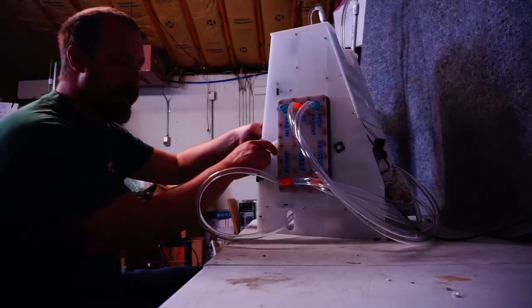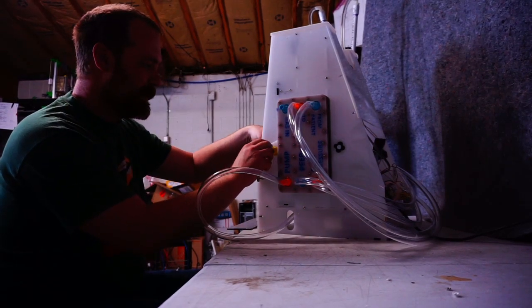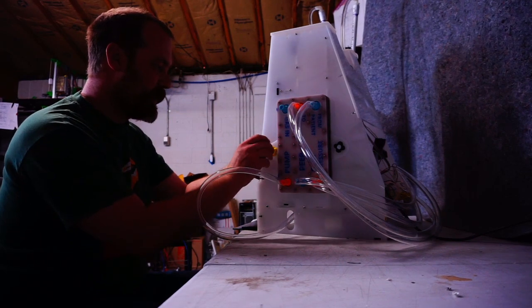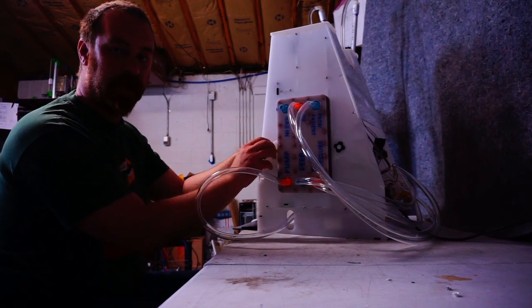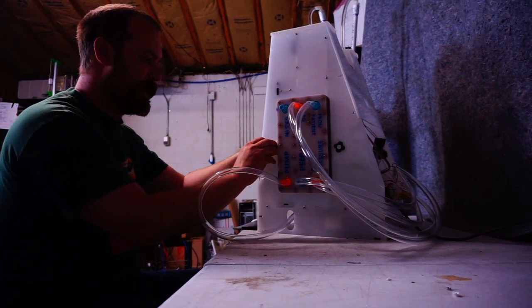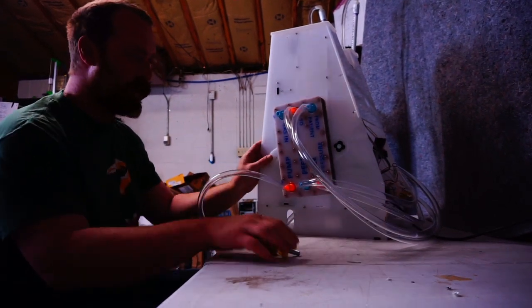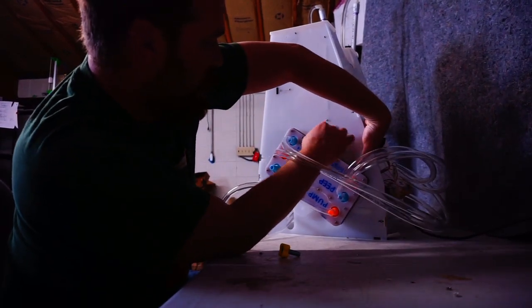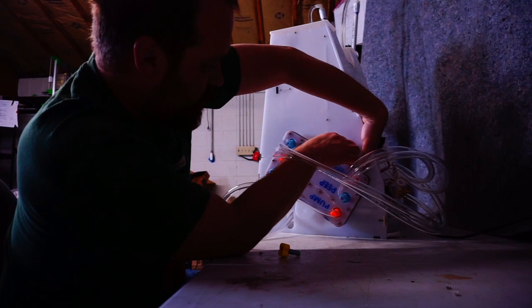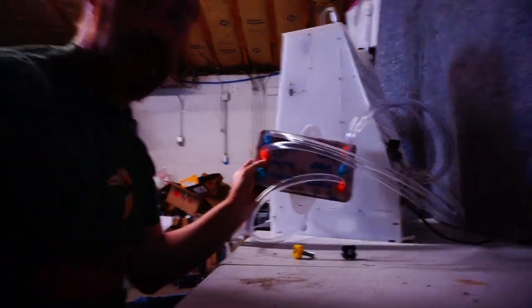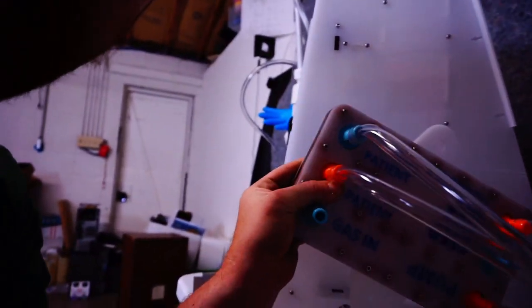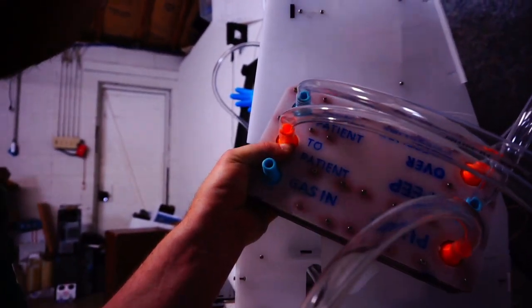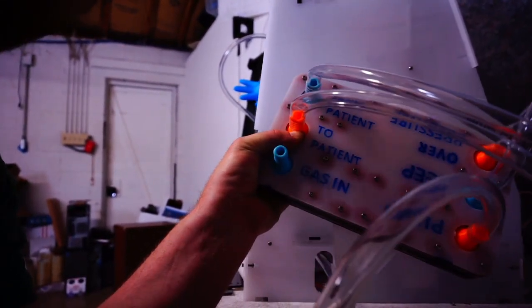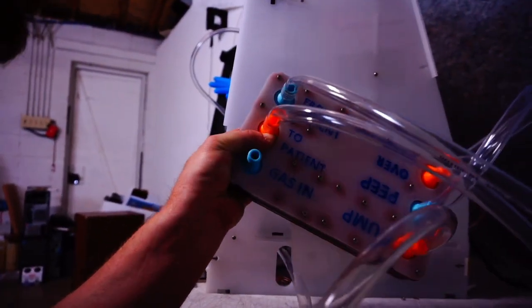And then this valve system, let's see if I can do this. This valve system is easily removable. Oops. Okay, off. Try not to get my fingers caught. Probably shouldn't do this while the valve is in use. It's got 2 screws, one on each side.